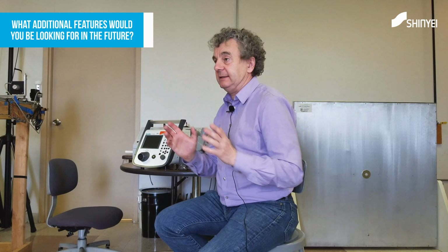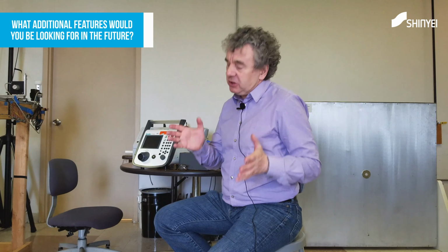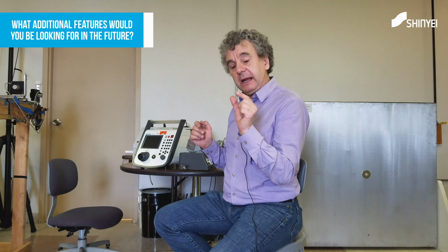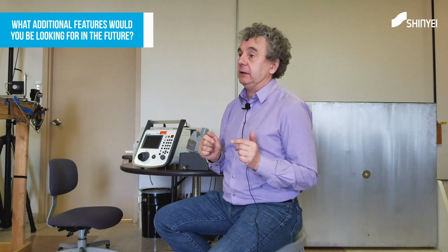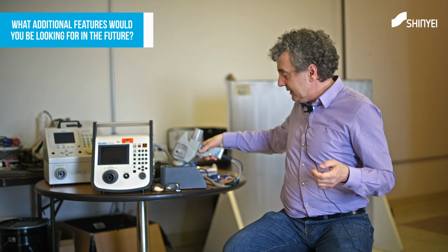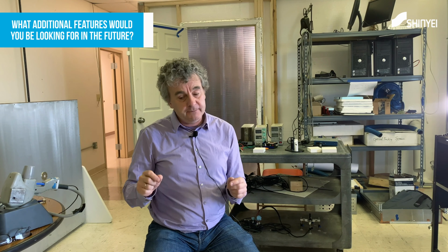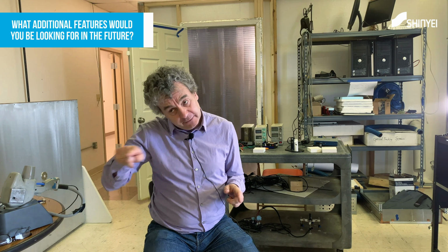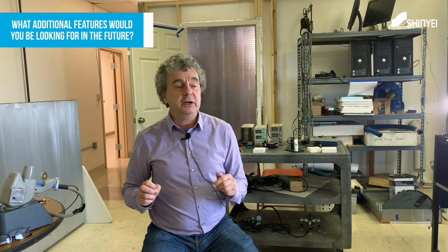Right now, ESD system level testing has the problem of bad reproducibility of results, especially in air discharge. In air discharge, the spark length for every discharge, even if you have the same approach speed, varies, and that causes a variation of the currents. So one thing which I think good test houses should do is measure the current. For every discharge, they record the current on an oscilloscope. And if a failure occurred, then they keep the waveform and can say, at this waveform, the DUT had this reaction, like it reset. In addition, I think one should have video recording.